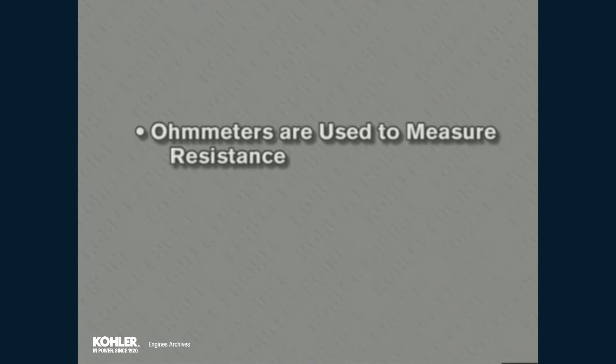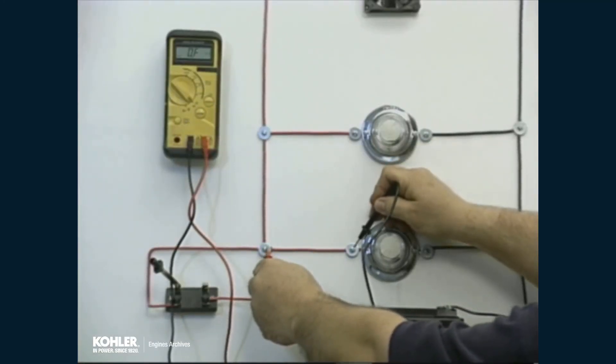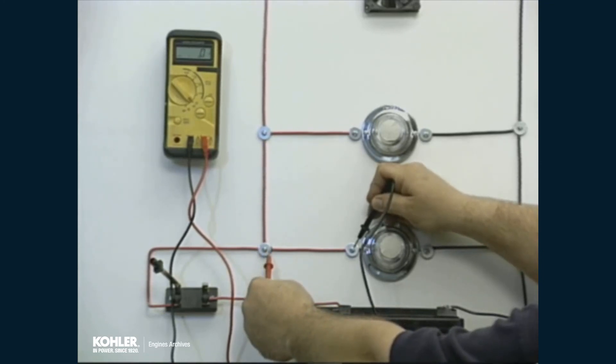Ohmmeters are used to measure resistance in components or sections of a circuit. An ohmmeter supplies its own power to the component or circuit being tested, so an ohmmeter should never be used in an active, powered circuit. Like voltage, resistance is measured parallel to the component or circuit being tested. An ohmmeter is connected to each end of a segment of the circuit that is suspected to have a circuit fault, and the resistance in that segment is read in ohms.